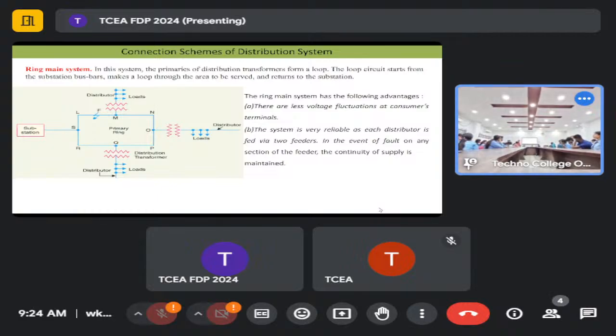This is the substation, and this is a fault that occurred. This is a distribution transformer — from this ring, this transformer gets power and gives it to loads. This is another distributor, this transformer gives loads. This is another transformer taking from this ring, giving loads. This is the distributor. Now if a fault occurs here, each and every distributor has the option to get power from two sides. But in case of radial distribution, you won't get that — if there is a fault, the entire line is off until the fault is cleared.